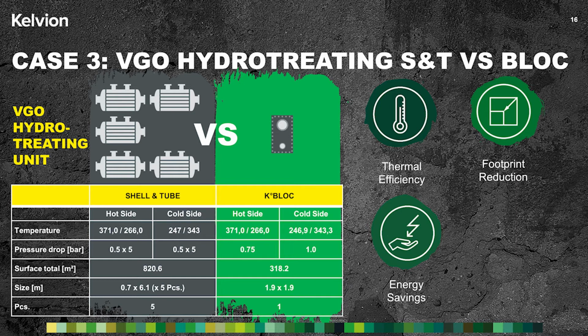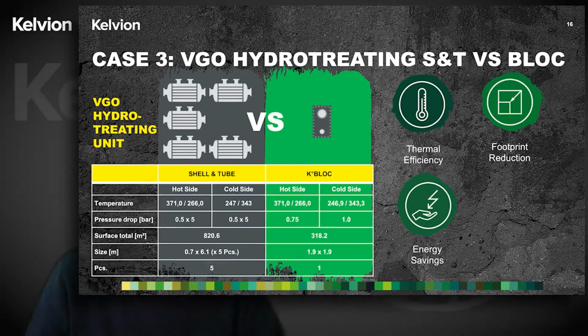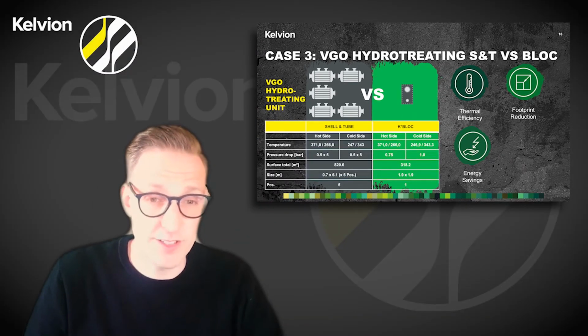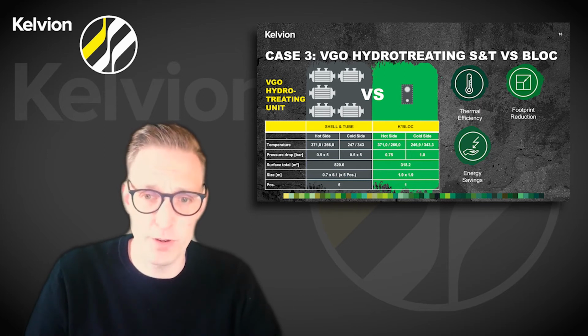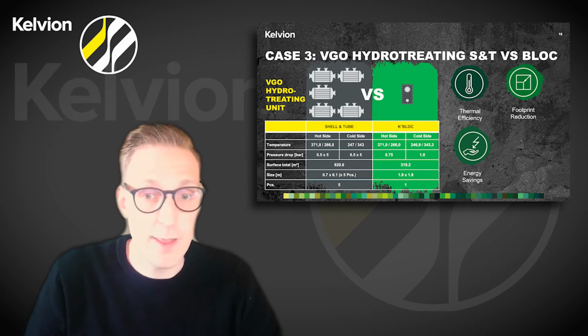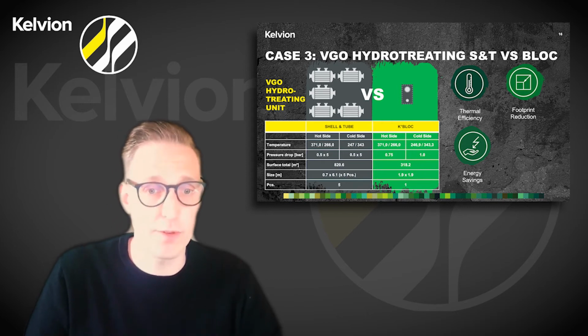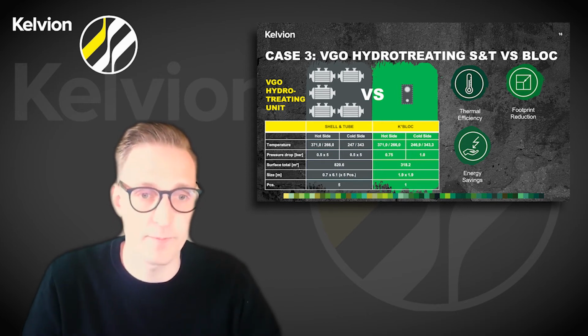1 K°Bloc is able to perform instead of 5 shell and tube units in series. The K°Bloc achieves the same heat recovery, but with lower capex and a lower footprint. In addition, the K°Bloc has a much lower pressure drop, which reduces energy consumption on pumps. 1 bar or less with the K°Bloc versus 2.5 bars for the shell and tubes. So, as a summary, the total investment costs for the new plant could be kept at a lower level, and the K°Bloc provides the operational reliability for a long lifetime.